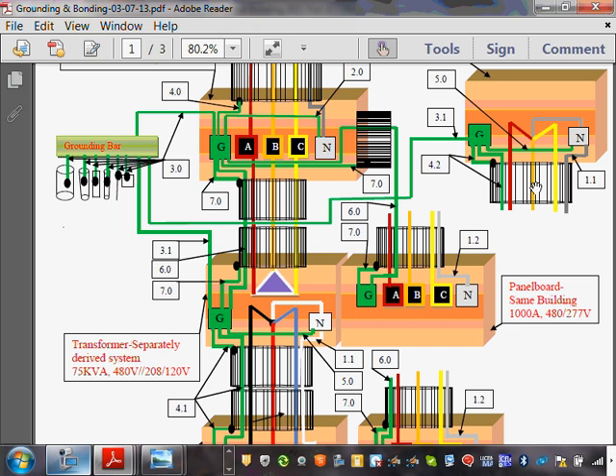If you're not utilizing the neutral, meaning you're not tying anything to the neutral, all you're feeding is three-phase, nothing is single phase. Then, yeah, you bring it to the first disconnect, which is typically on the transformer. You bond it there and leave it. Your utility service already has a neutral in it that's bonded.